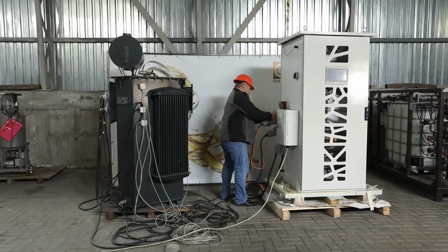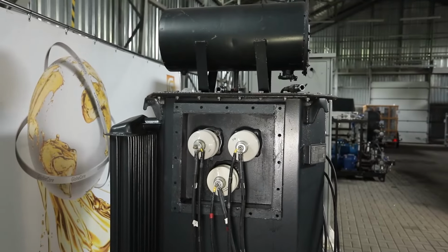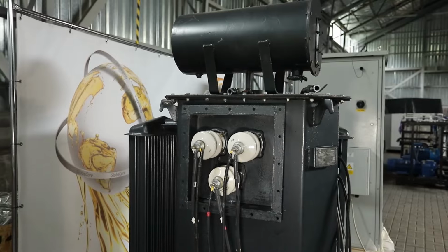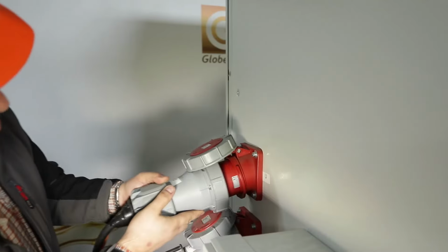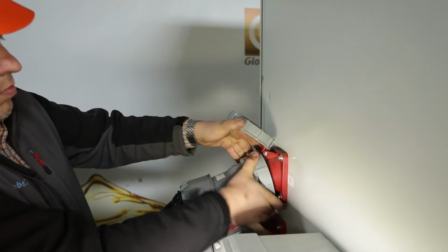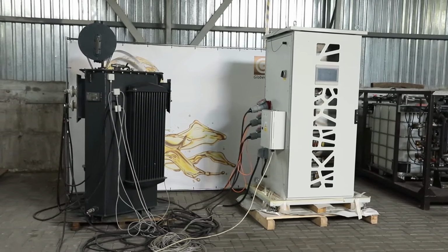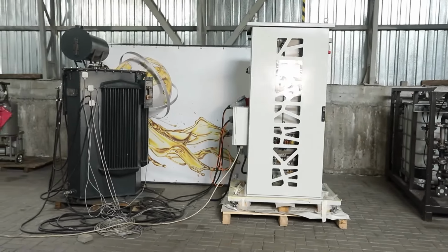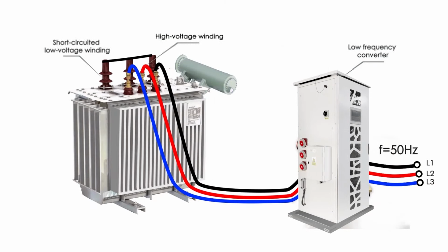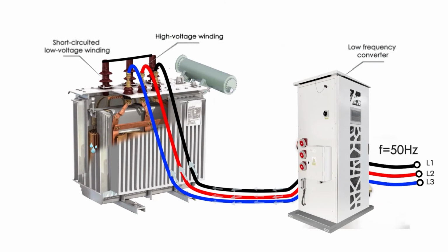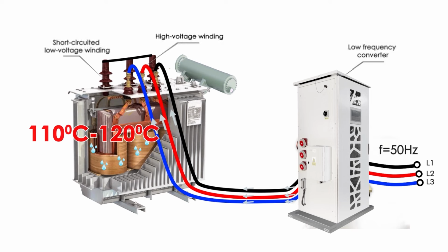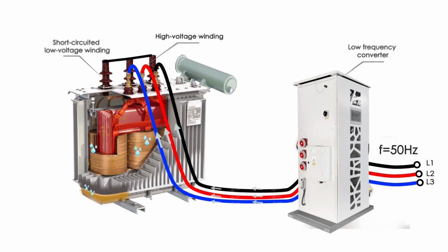Due to the magnetic coupling between the high and low voltage windings, a controlled current also begins to flow in the low voltage windings. As a result of the flow of low-frequency currents, the high and low voltage windings are heated from the inside to a typical drying temperature of 110 to 120 degrees Celsius. To prevent overheating, the temperature of the windings is constantly monitored during the drying process. Due to the fact that when heated by low-frequency currents, the heat source is the winding itself and the heating comes from the inside, the removal of water from the thickness of the insulation proceeds faster and more completely in comparison with other heating methods.